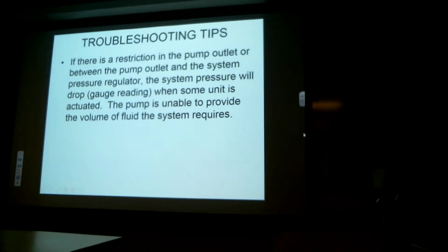That's one thing. If there's a restriction of the pump outlet in the system pressure regulator, the system pressure will drop. This is kind of a strange thing that happens with a lot of hydraulic systems. The gauge responds, of course, to system pressure, but it also responds to flow in a way. So when some unit is actuated, and maybe there's a blockage or a kink in the line, the system pressure gauge will initially indicate a drop in pressure. So it says, if there's a restriction of the pump outlet or between the pump outlet and the system pressure regulator, the system pressure gauge reading will drop when some unit is actuated. The pump is unable to provide the volume of fluid that the system requires. So sometimes, again, it isn't just pressure that it's indicating, it's really indicating a restriction that might be in the circuit.